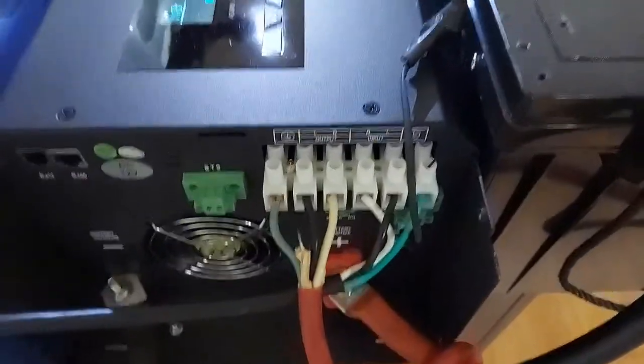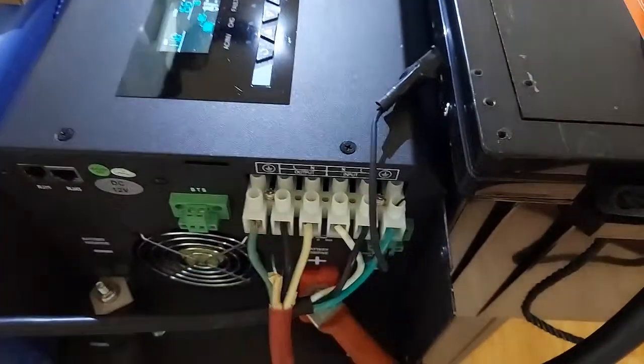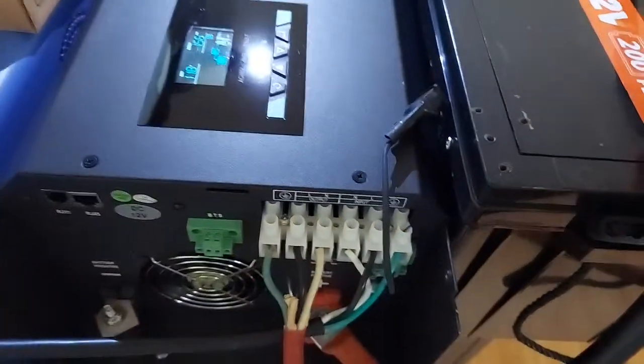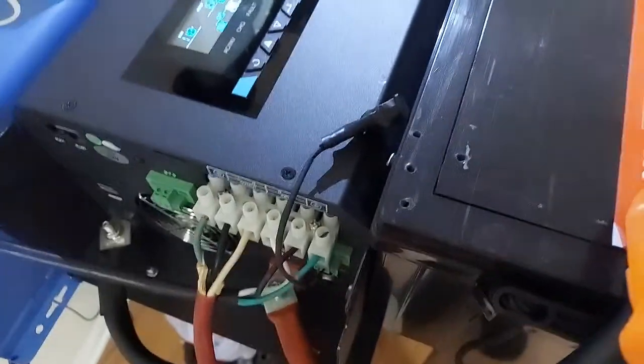That's a 20 amp GFCI. It's a 12 gauge cable. And the cable going to the terminal block is actually 10 gauge coming off the board, and the relays are rated for 40 amp at 277 volts. So this thing's built pretty good.